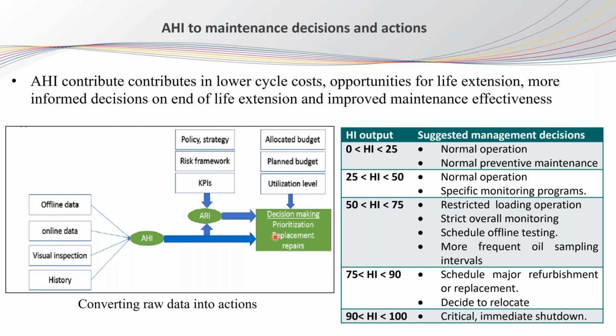But the challenge here is that your decision is always limited according to the allocated budget and the planned budget. So you may need to do a prioritization based on these two values. Just as an example of how the health index can be used to provide management decisions: if you have a health index from 0 to 25, you can consider normal operation and preventive maintenance. But if you have a health index from 90 to 100, in this case, you may consider immediate shutdown. In between, you can consider restricted loading operation, more oil sampling and other actions.